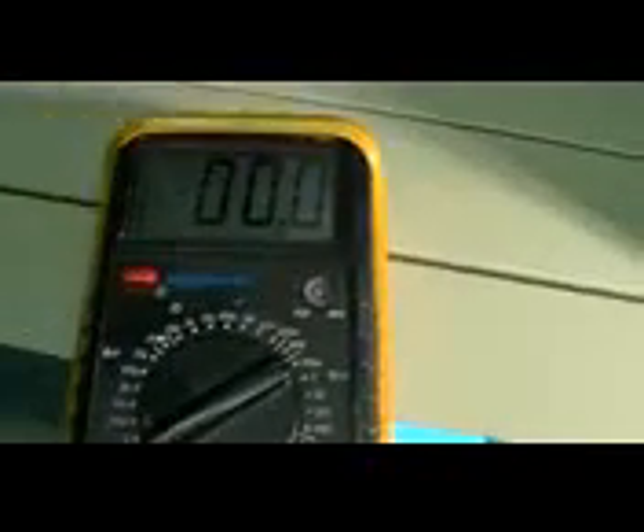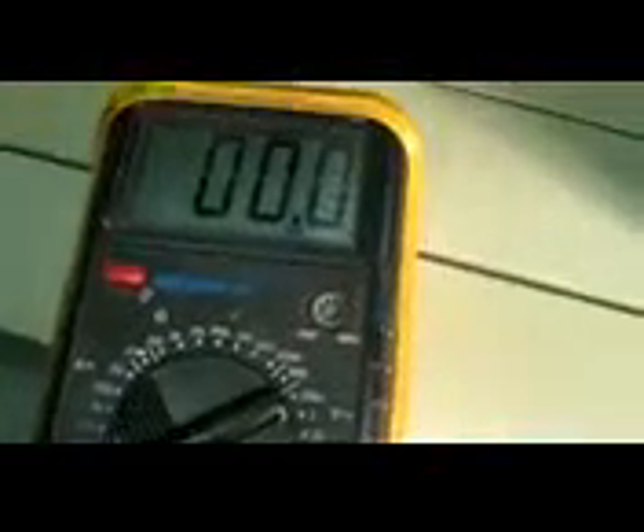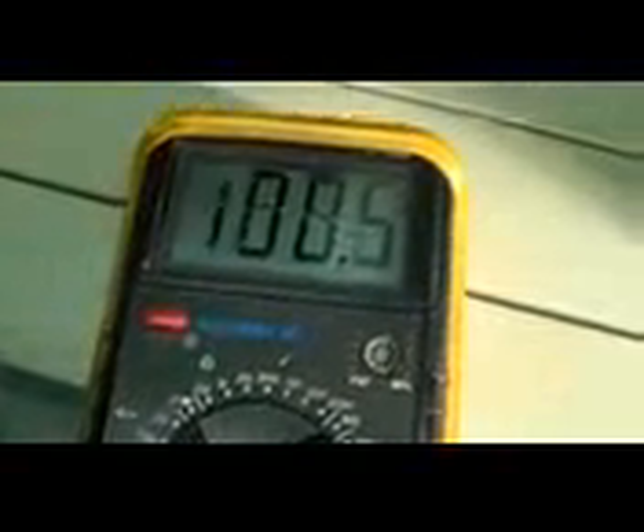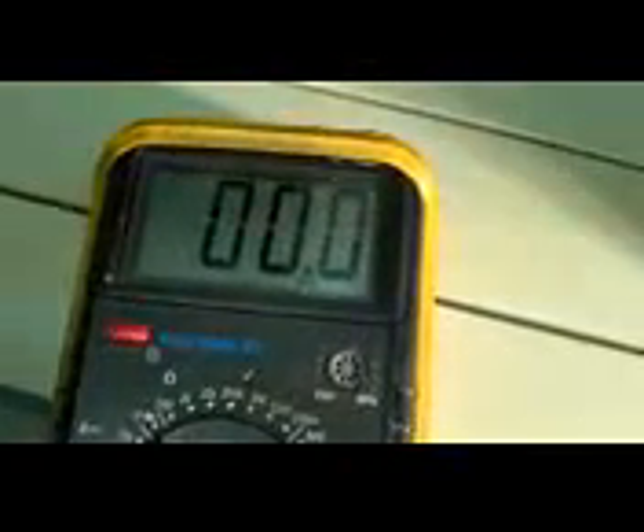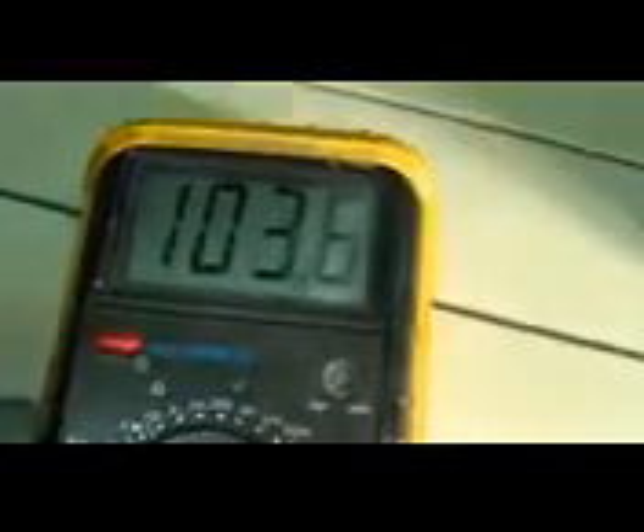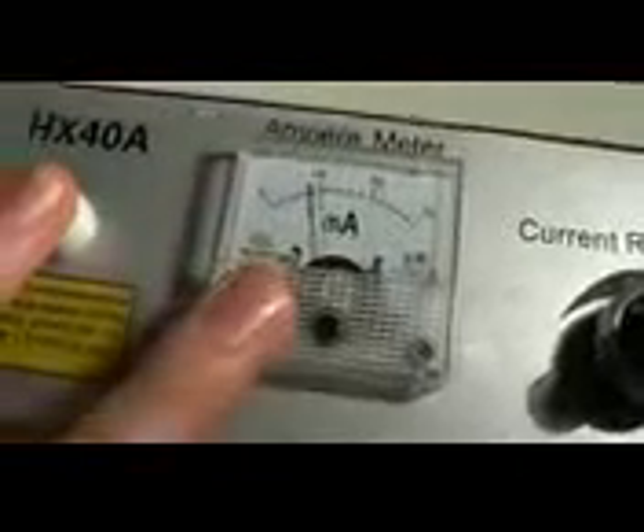Here I've got the meter connected across the sense resistor, and it's measuring on the millivolt scale. When I fire the laser, it reads correctly - that's reading 10 milliamps there, and we're dividing it by 10, and the meter on the front panel is reading 10 milliamps as well. So that shows it's working correctly.